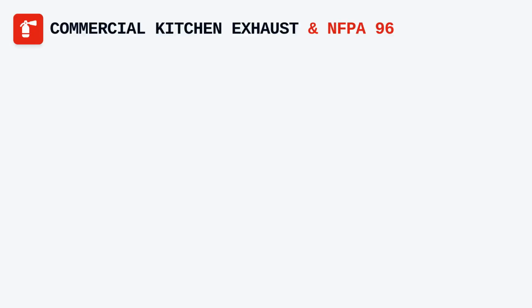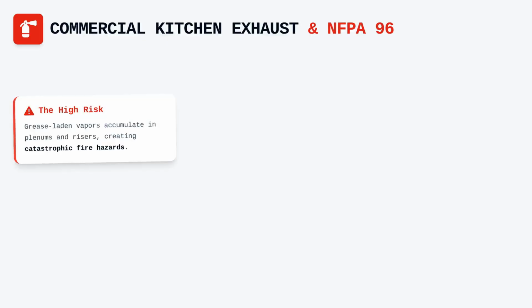Commercial kitchen exhaust systems represent a specific, high-risk category governed largely by NFPA 96. Unlike general ventilation, kitchen exhaust is designed to transport grease-laden vapors from cooking surfaces to the outdoors. The accumulation of these residues is a primary fire hazard, and maintenance protocols here are not merely about indoor air quality, but about life safety.